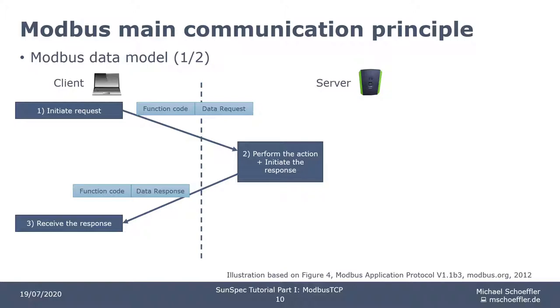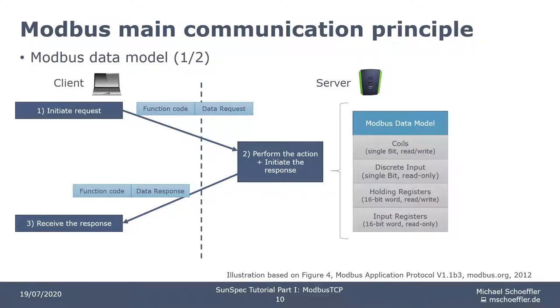Let's dive deeper into the topic of Modbus communication. I want to point out the Modbus data model. All the data accessible via Modbus belongs to a category: either coils, discrete input, holding registers, or input registers. Coils are data with a single bit — true or false — and can be read or written. Discrete input also has only a single bit, but can only be read. Holding registers are 16-bit and can be read or written. Input registers are also 16-bit, but can only be read.